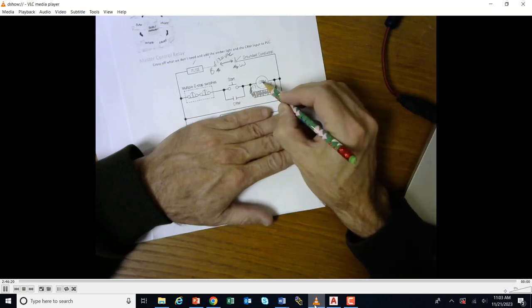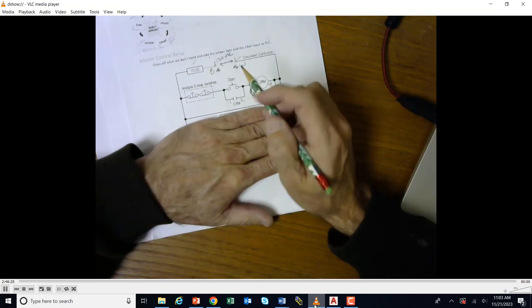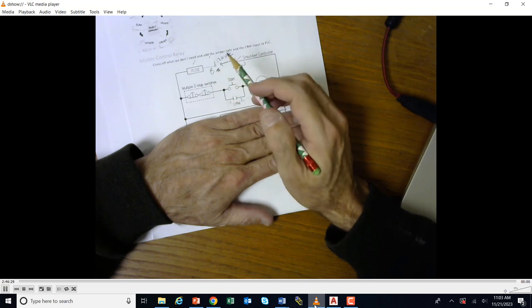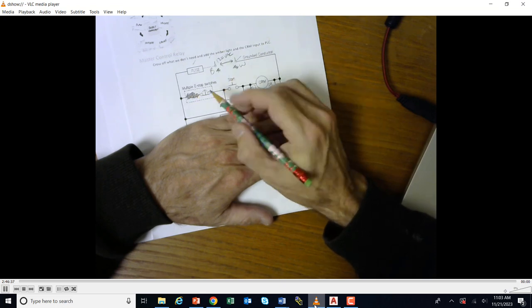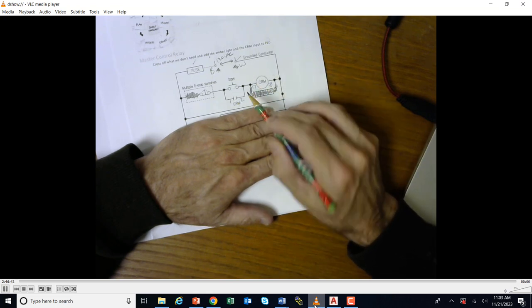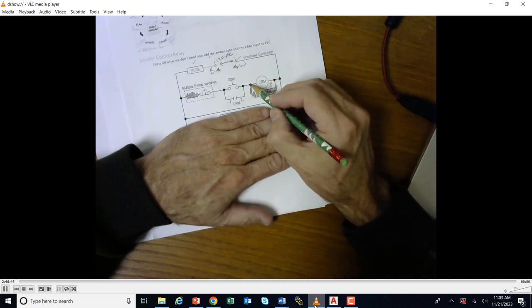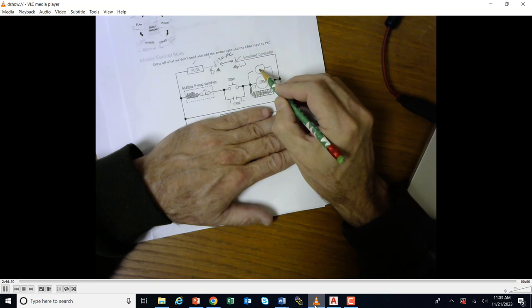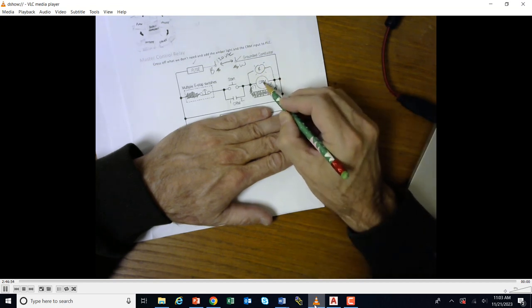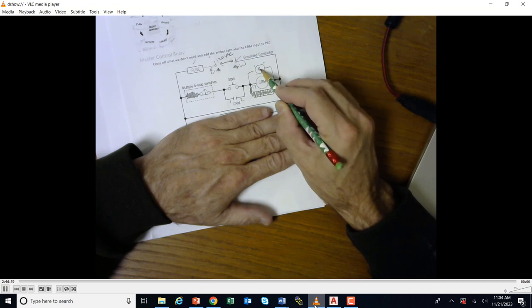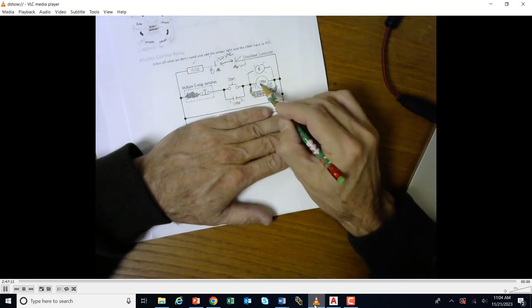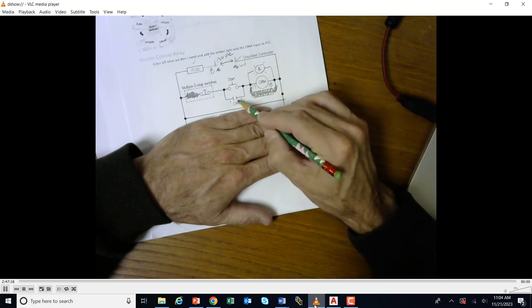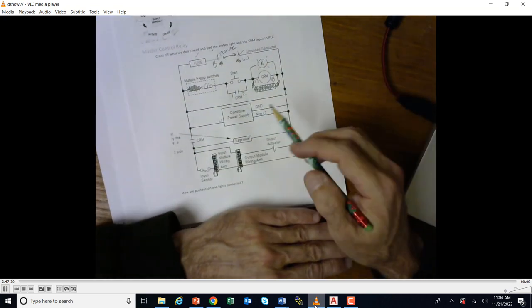The MCR contacts are 1 and 2. This has two stop buttons in the diagram, but we're just going to use one normally closed and one normally open. When you hit start, you get a holding circuit. I'd like you to put a light — maybe a red or green light — on the control panel so that when the MCR is on, the light comes on indicating main power is on. Hit start: it latches and the light comes on. Hit stop: the MCR shuts off and the light goes off.